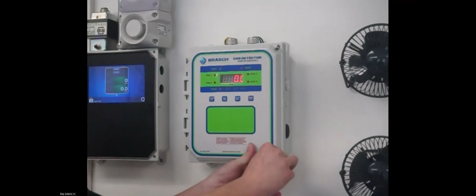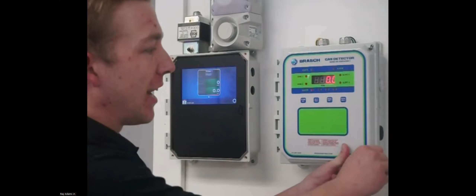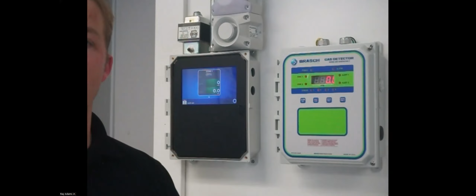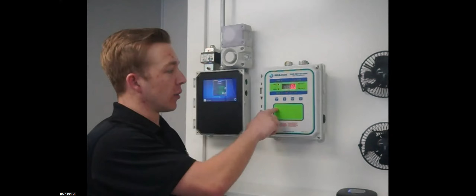It has rain tight conduit fittings on top and vented louvers on the side. For any condensation or moisture that may get into the unit, there are drain holes designed in the back, running along the back panel plate, to accommodate anything that gets in. The louvers on the side, and not having front-facing sensors, play a big factor here. Quite a few manufacturers have their sensing elements directly on the front of the unit with vents that allow air through, and whether it's a car wash or someone spraying down a vehicle, that allows water to get in a lot easier than draining down the side. That's what those louvers are designed to accommodate.